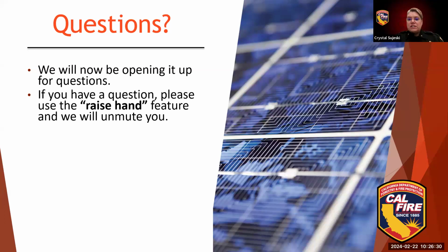That's a really great question that's still being discussed at the development phase of the I-codes, even here in California. I believe NFPA 855 gives a good checklist for the signage criteria, so AHJs, based on their response capabilities, would have to check with them to see what their folks want. It's definitely something they should look out for - same thing with PV systems. We want to know where the shutdown is and where the disconnects are, and the signage is going to be per the AHJs.